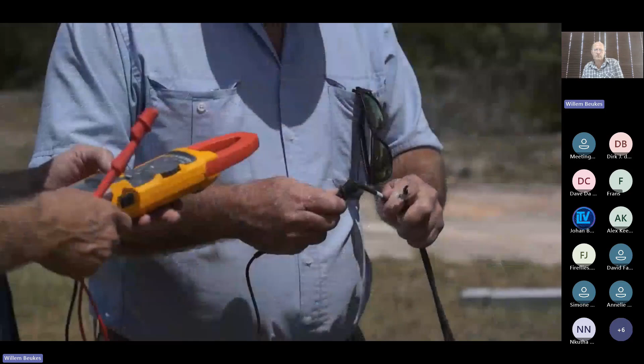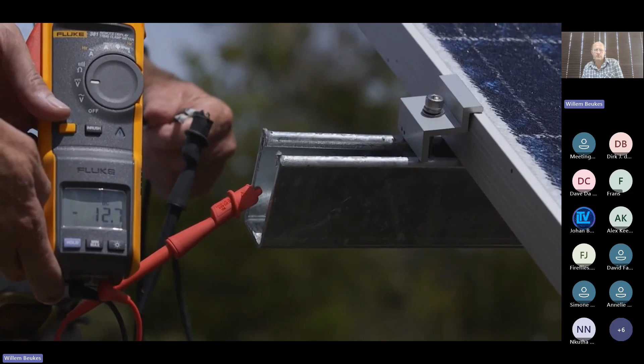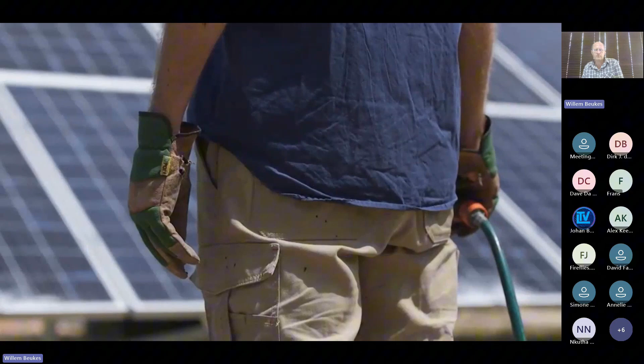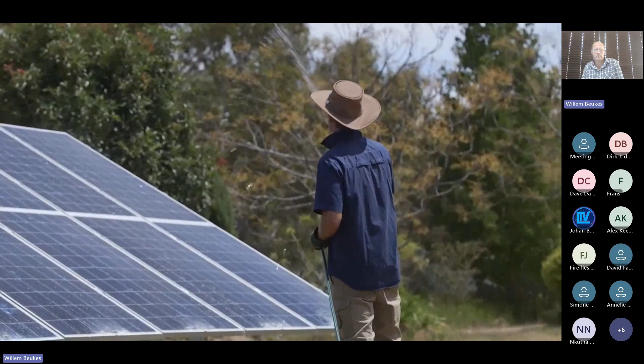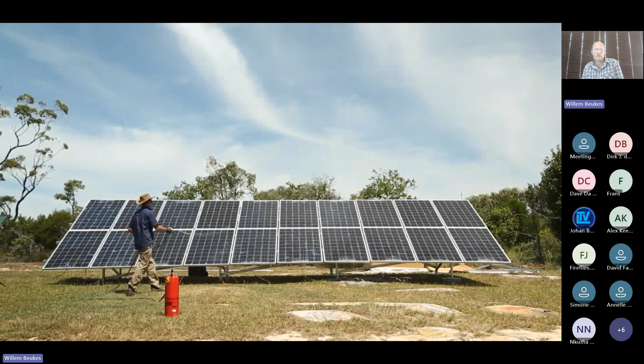Next, we connect the voltage meter and the amperage meter to the solar panel frame to determine if the damaged panels are leaking electricity onto the frame. The voltage reading is only minor at between 12 and 15 volts, which poses no serious threat of injury. To simulate rain associated with a hailstorm, or water being applied to an incident involving fire, we then apply water to the damaged array to see if water conductivity affects the amount of electricity that leaks onto the solar panel frame. The impact of water is dramatic.